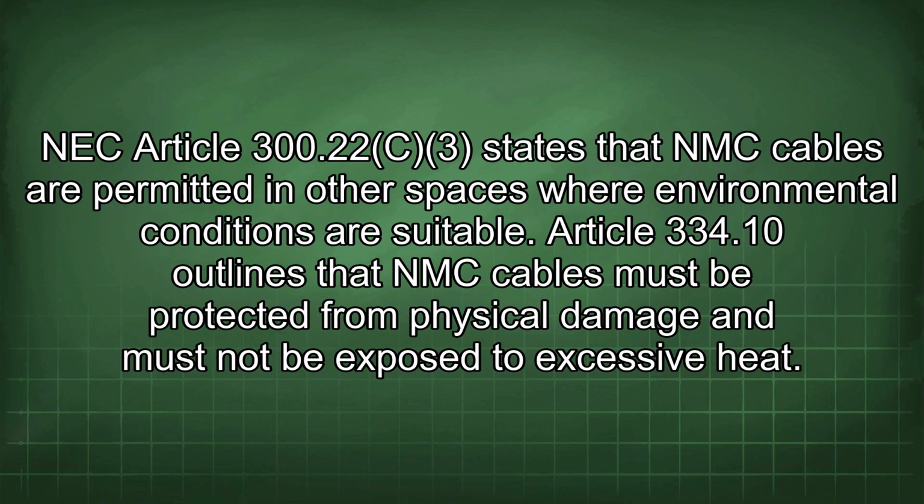NEC Article 300.22(C)(3) states that NMC cables are permitted in other spaces where environmental conditions are suitable. Article 334.10 outlines that NMC cables must be protected from physical damage and must not be exposed to excessive heat.